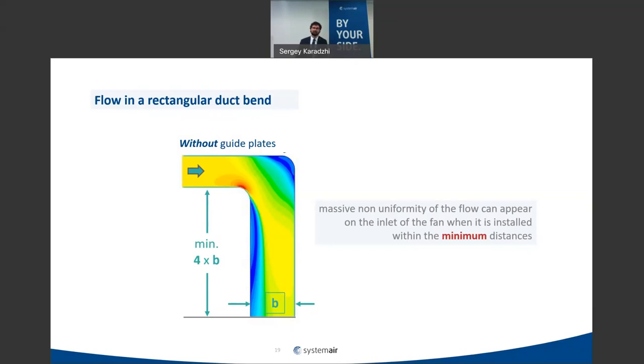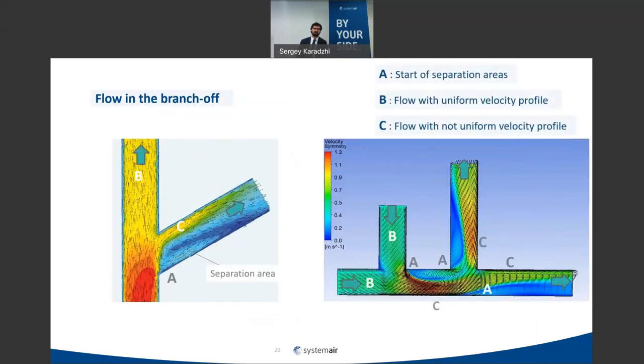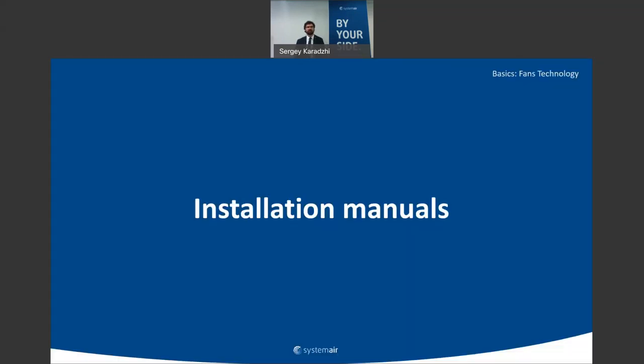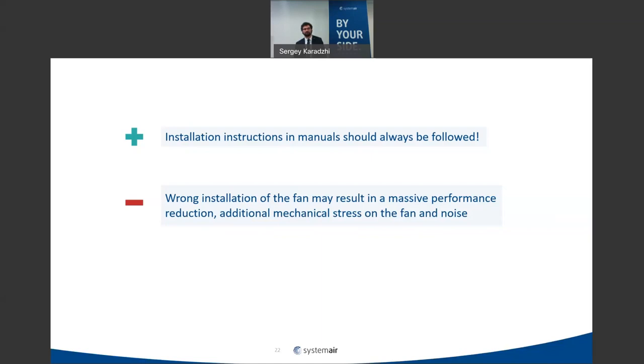Similarly, a branch-off from a duct also creates separation, and it is not recommended to install a fan near a branch-off, as this will reduce the fan's pressure curve and increase sound and vibration. Installation manuals come with the fan and should be followed, because wrong installation can change the fan's curve.